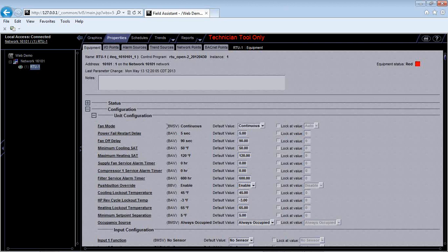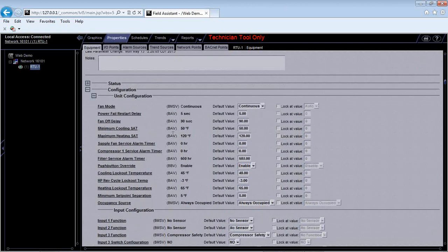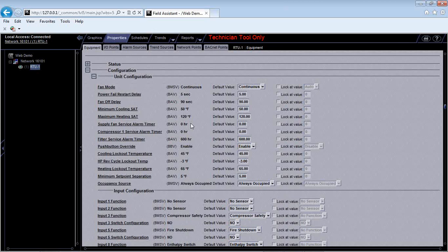There's a couple different safeties here. Power fail restart delay is just a 5-second restart delay if you lose power. My fan off delay is if my fan's off, I'm going to wait 90 seconds before I turn my fan back on. You can mess with those. I usually just leave them as defaulted because that's what Carrier recommends for their units. Couple items we want to look at that are kind of important here are the minimum cooling supply air temperature and the maximum heating supply air temperature. Okay, so I can type in and change these values to what I want, but we default to 50 and 120. Okay, so if you unfortunately have an oversized rooftop unit and you're getting discharge air below 50 degrees, you're going to want to lower this value.